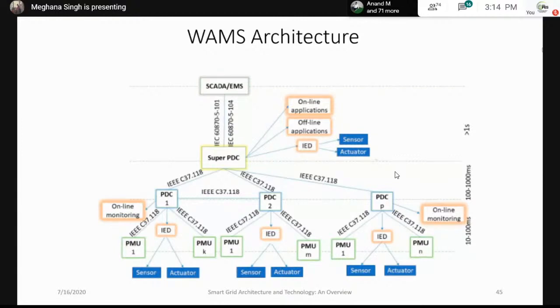One thing you need to understand: sensing and actuation should be done within 10 to 100 milliseconds. Online monitoring is very important. The time window is 10 to 100 milliseconds. Then from PDC to super PDC, it is 100 to 1000 milliseconds, and from super PDC to SCADA, it is greater than 1 second. So time is very important for a PMU when it comes to a wide area monitoring system. You have to sense the data within 10 to 100 milliseconds. Next slide, please.